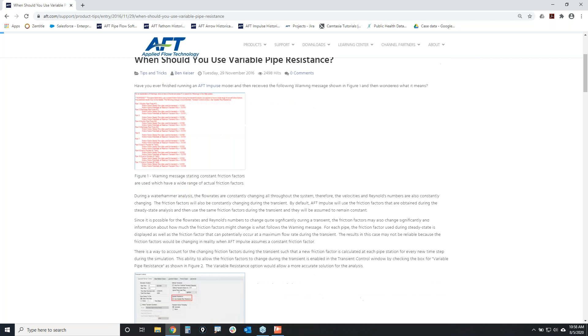If you're doing a transient simulation and your flow rate is changing, your Reynolds numbers are changing, your friction factors are going to change. Typically, they're not going to change very much. And so what this is telling you is the initial friction factor in steady state flow, and then what the friction factor could be at maximum flow. And so as your flow rate gets higher, your friction factor would potentially decrease. And so the issue is, if your friction factor changes a lot, would you want to continue using the steady state friction factor value for every time step in the simulation? And you may want to allow that friction value to be able to change.